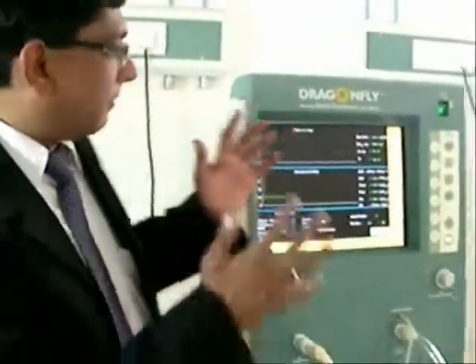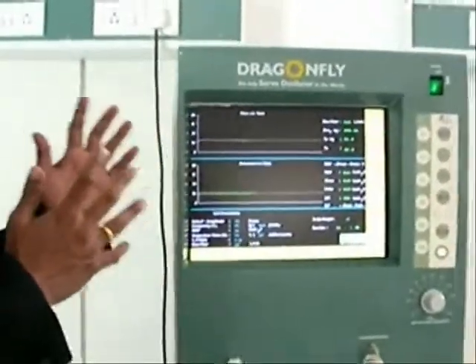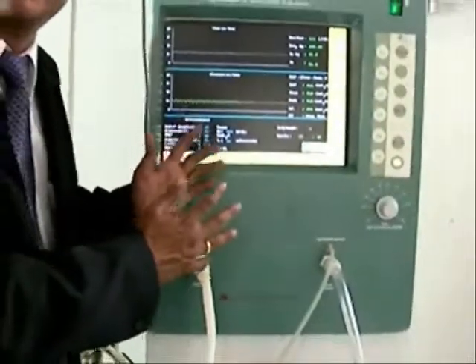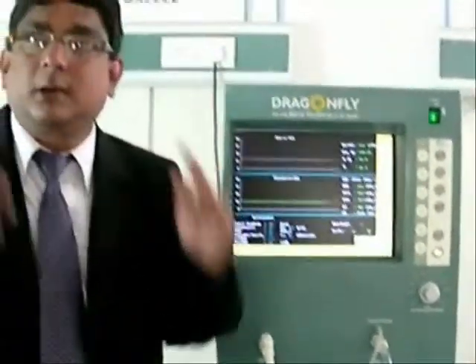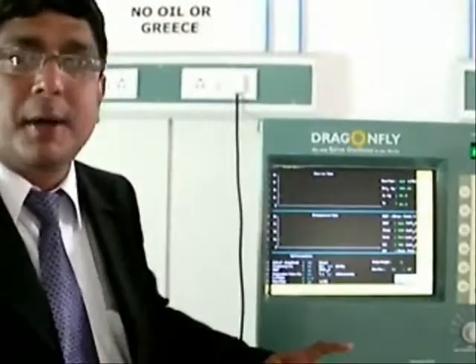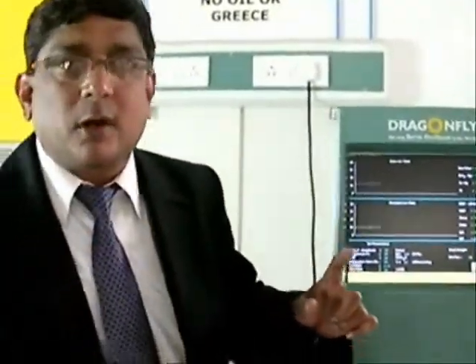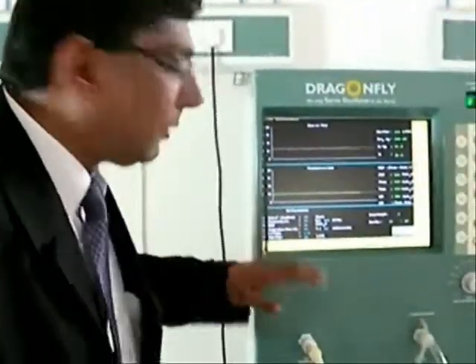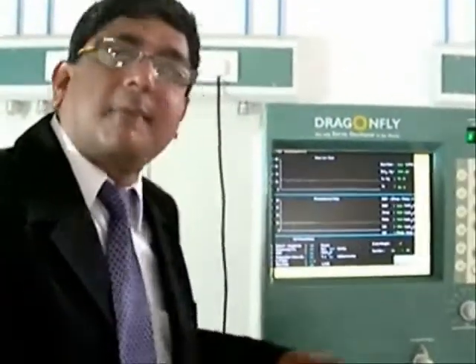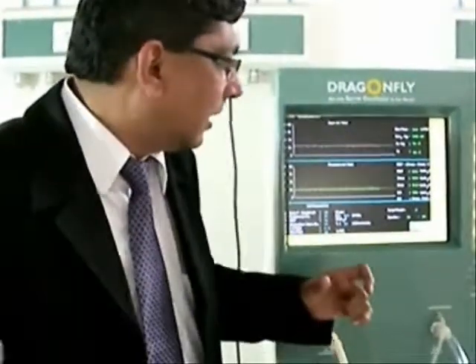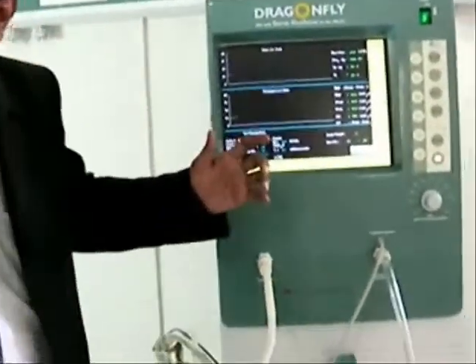So I'm quite proud to present to you the high-frequency oscillatory ventilator, in which inspiration and expiration are both active. You can set the mean airway pressure from 4 to 40 centimeters of water. You can set the amplitude from 0 to 100%. That's the power given to the piston to move to and fro. Third is the frequency, which you can set from 5 to 18 hertz. And the inspiration time from 33% to 50%, that is, an IE ratio of 1:1 and 1:2. It's that simple, my dear. Thank you.